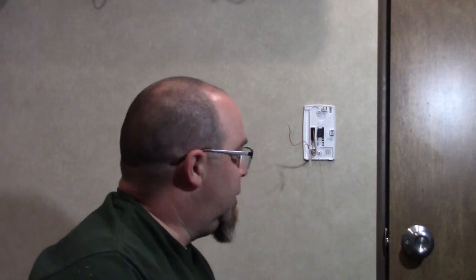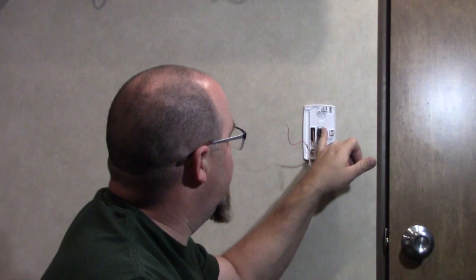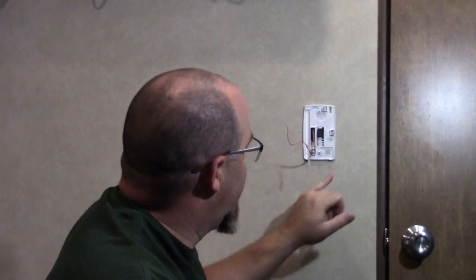All right I'm back with you, got my micro screwdriver. We've got three terminals in the thermostat housing, we've got to attach two wires to. It's labeled W and R but I go back to what I said originally, color codes don't always match. Don't go by the letters and don't expect that R is red and W is white, it could be the opposite. So we'll end up checking our instruction manual. Our white is our heat relay and R is our power. On that unit we need to supply 12 volts to the power supply.